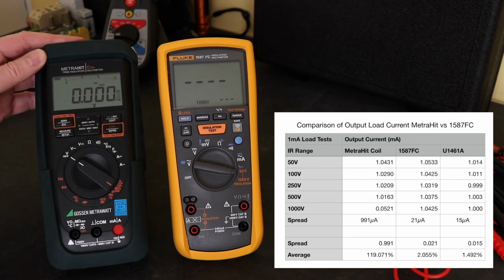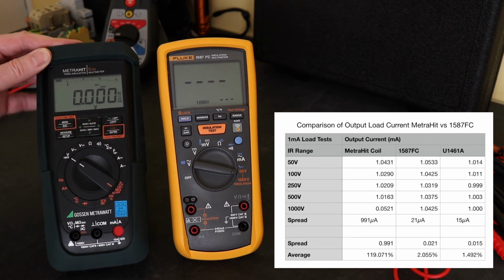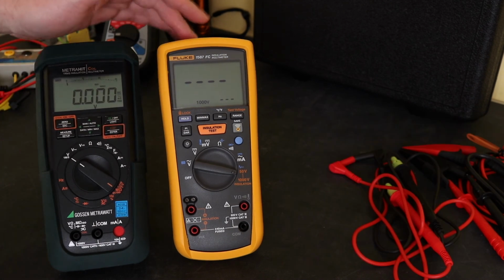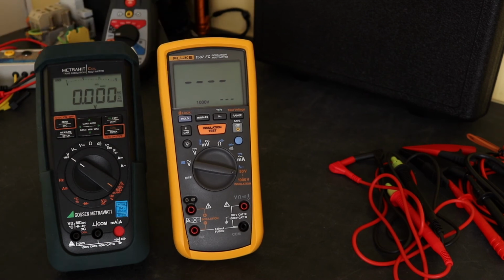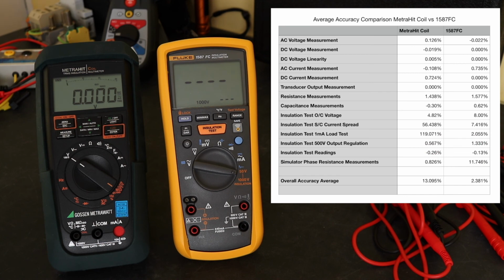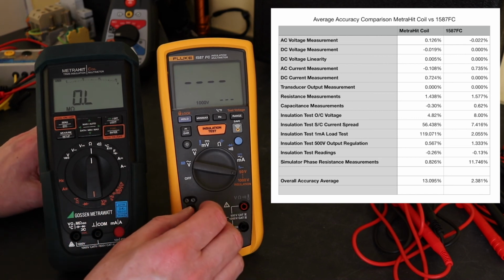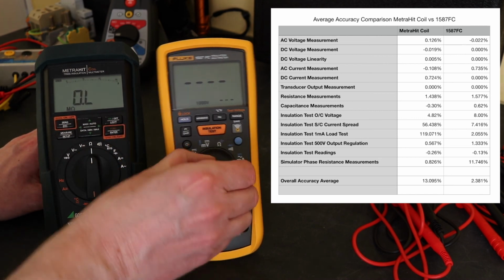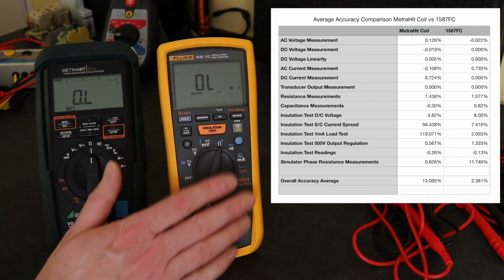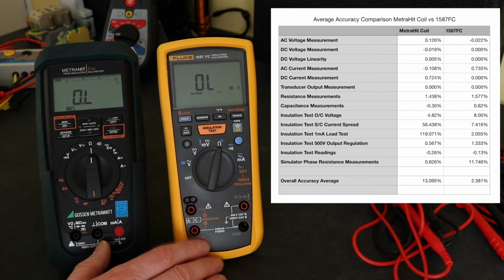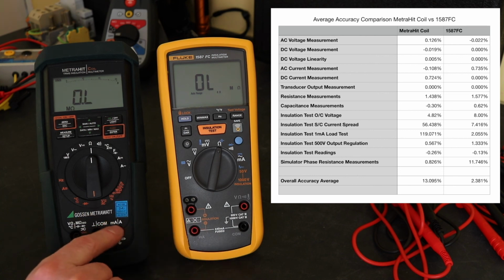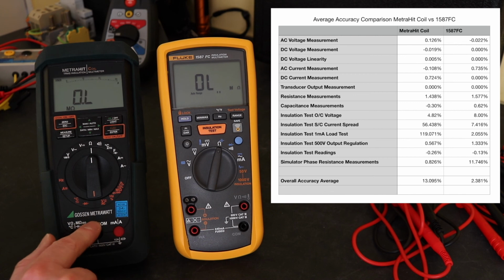So this instrument at 1000 volts insulation test does not pass the IEC test requirements. It does pass it on all the other ranges, whereas the Fluke passes it on all the test voltages, including the 1000 volts. For the actual voltage regulation, 500 volt test, not much to choose between the instruments really, fairly happy with that. And then we go to the winding simulator and measuring the phase resistance as a practical test, and you get much better results from the resistance readings of this instrument than I do from that one. You've got quite a bit better resolution on this instrument as opposed to the Fluke here. I don't know why I did that, because they're both on overload, aren't they? However, both of these are 1 milliamp test current. Neither has the 200 milliamp test current. Again, that's another requirement of my country for continuity testing, to have a 200 milliamp test current.